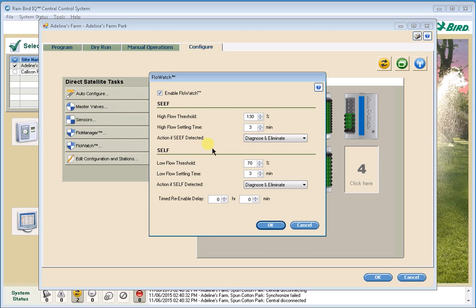The next setting is the action if SEEF is detected. So if we see 130% higher than expected flow rate for at least three minutes, the default action is Diagnose and Eliminate the Problem. What IQ will do is pause — basically shut off the stations that are currently running, close the master valve, wait a little bit, then turn the master valve back on. It looks at the flow sensor, and if there's no stuck valve or mainline break, the flow should be zero. If it does see flow, we have a stuck valve or a mainline break, and it will re-close the master valve and issue a mainline break alarm.